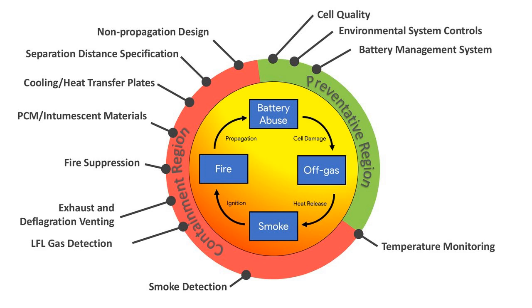If we populate this chart with some of the typical fault detection, suppression, and control methods used within industry, you start at the top, and it always starts with cell quality. Quality cells kept under control within manufacturer spec is where the primary control within the battery system comes from. As you go around the wheel into the containment side, on smoke and fire detection, this is where most of the fault detection specified within current standards comes in. You have smoke detection through fire suppression, and then you get into what is really the non-propagation design. What you're trying to do is prevent a failed cell from failing adjacent cells within the system and leading to propagation.